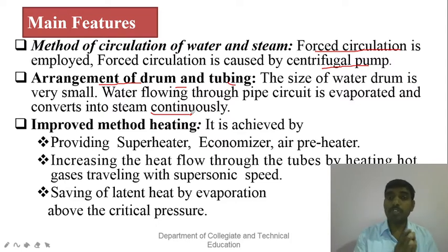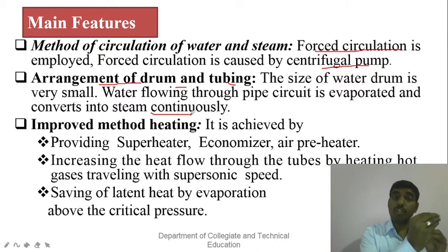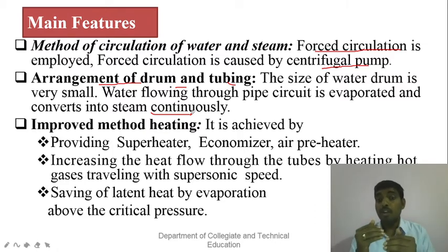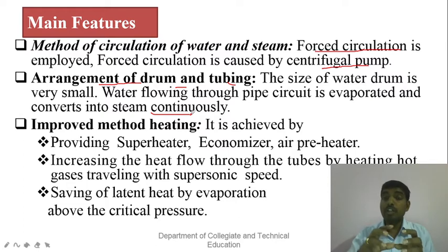As seen in the previous video, we have a steam drum. Here the feed water coming from the economizer flows down to the downcomer. Again when the water is converted into steam, it flows back to the steam drum. There is also a water-steam separator that will separate the steam from the moisture content. Again the separated water will go down to the downcomer. In a similar way, the drum is very helpful in the high pressure boiler.